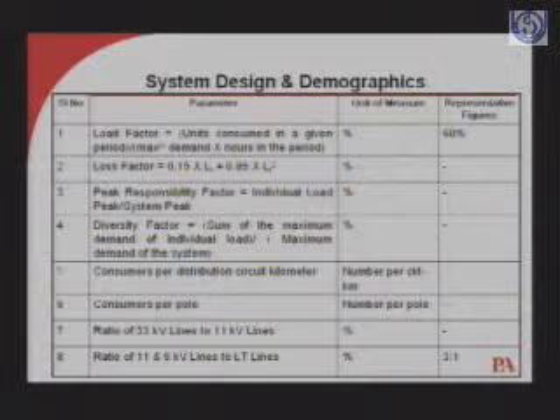But how to get this loss factor? The formula is a very empirical formula: 0.15 into load factor plus 0.85 into load factor square. That's how you have to calculate. Meaning thereby, if you do it that way, you can calculate the technical losses that are there in a circuit.